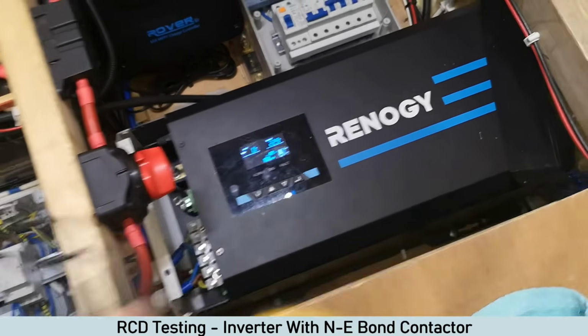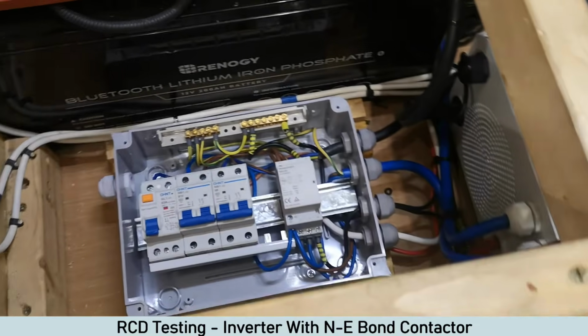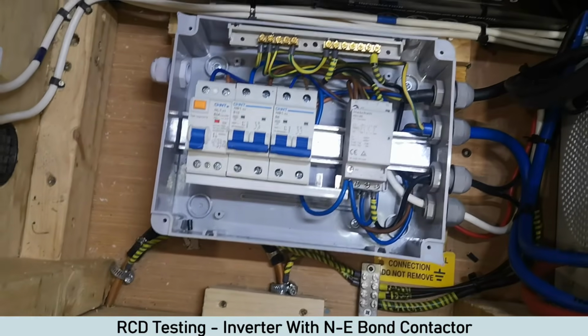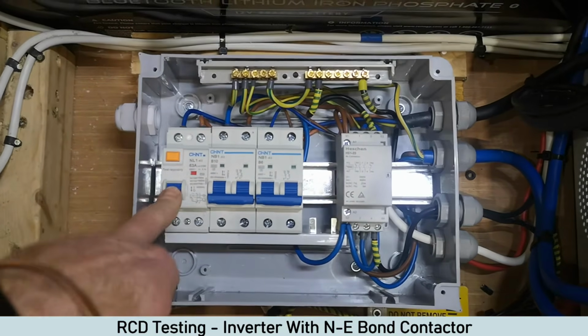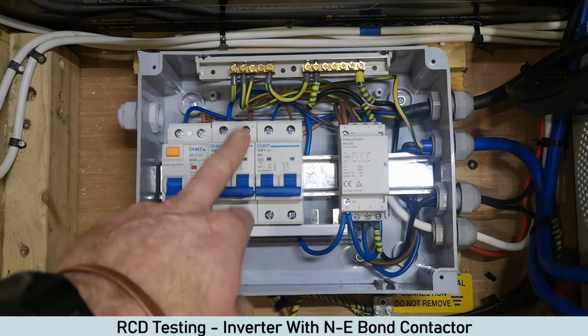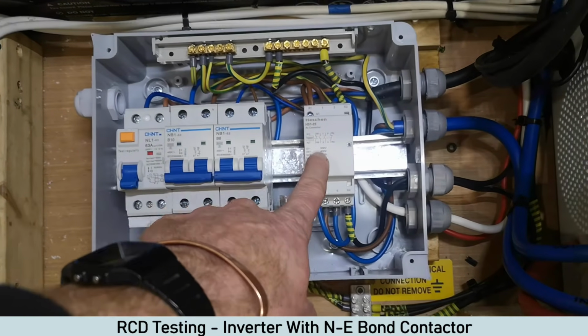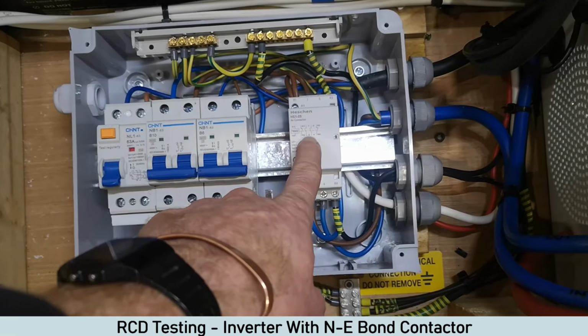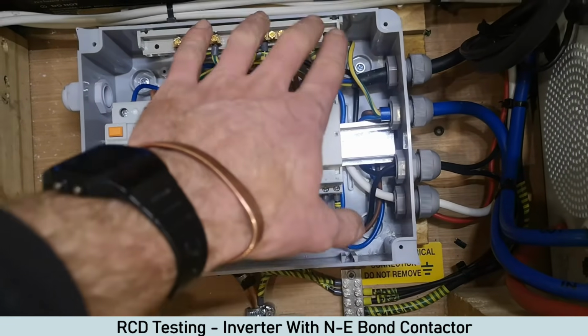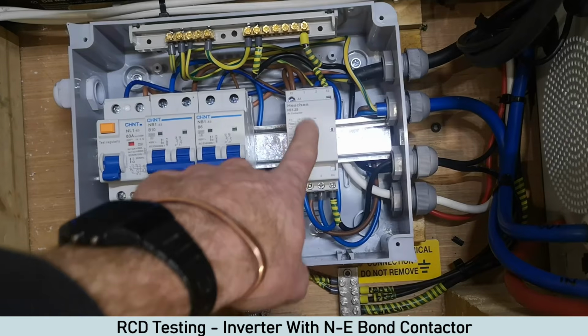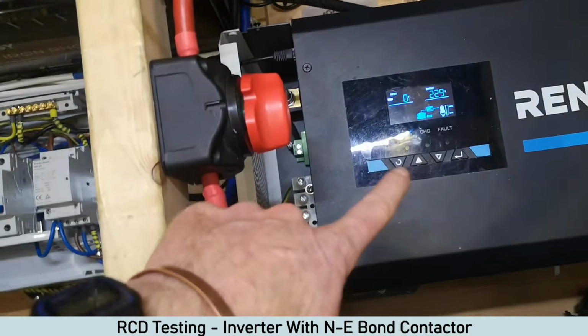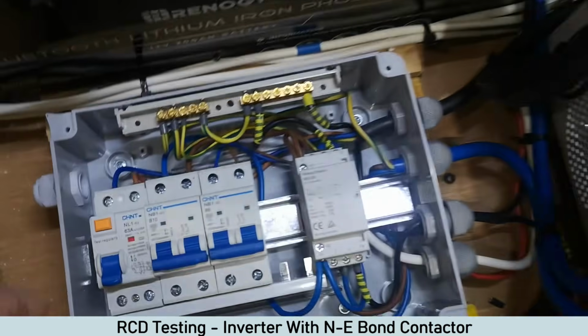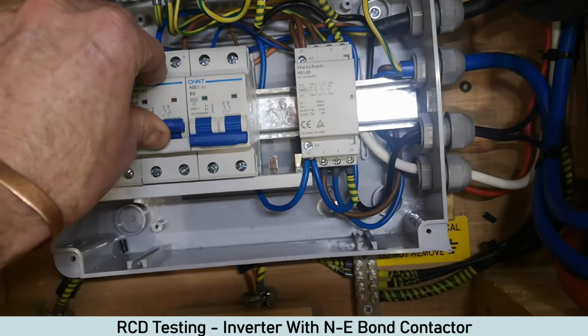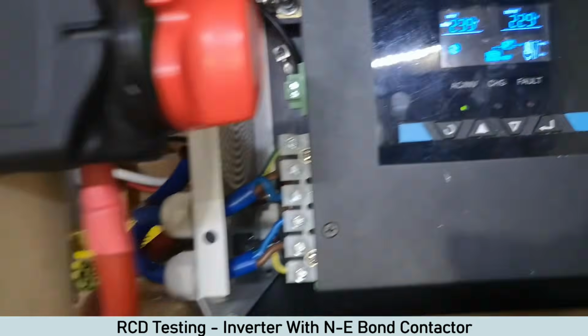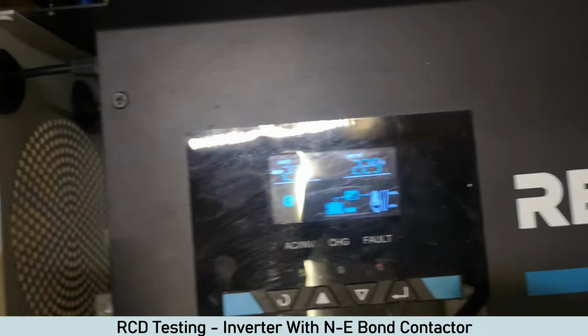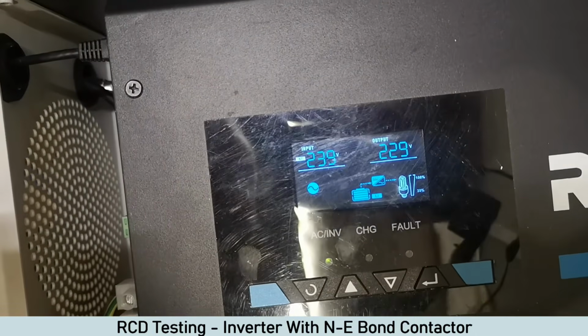Then what I'm going to do now is switch the hookup on, and we'll see what happens. So I'll turn that on, turn the power on to that. Once the power comes on to that, this will flick on, so it'll open the bond we've got now, and it will close the contacts, powering up the inverter charger. So you may hear a click. That's on. We'll just see what happens with this. It takes a second to kick in.